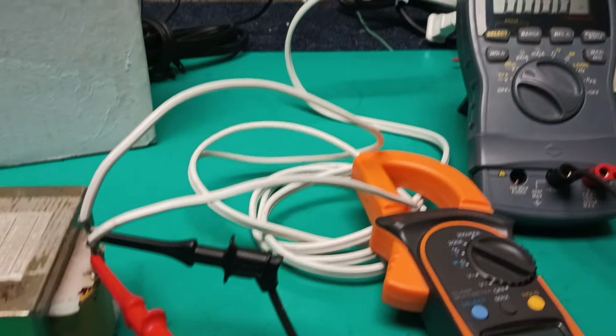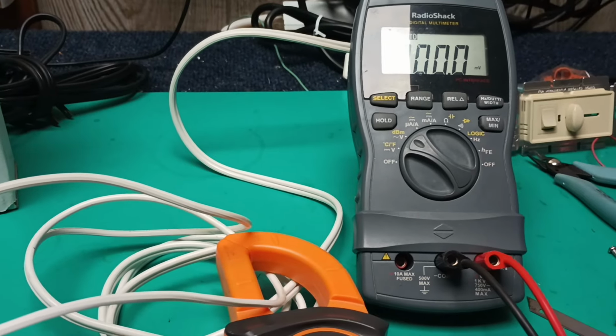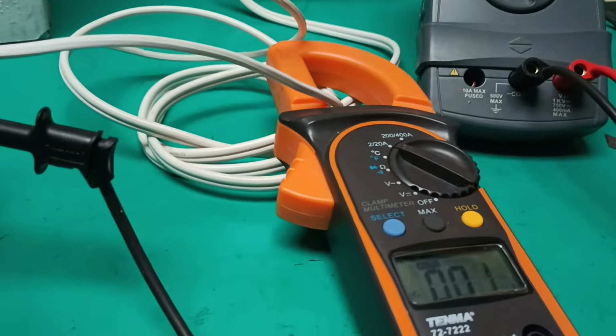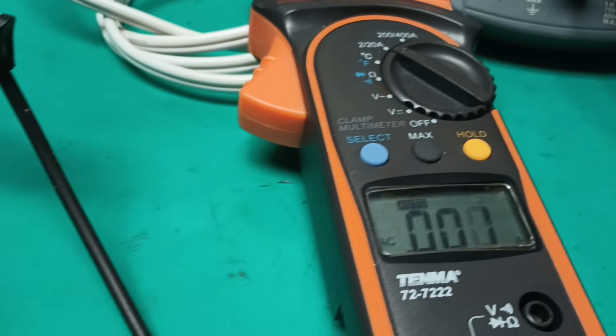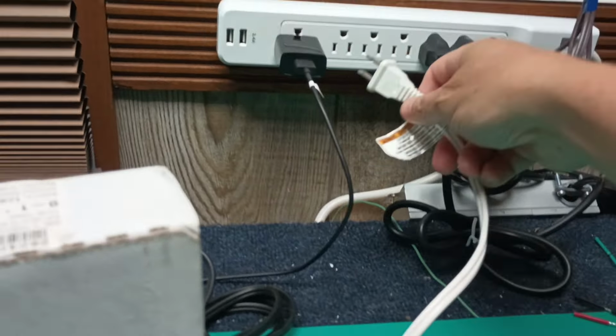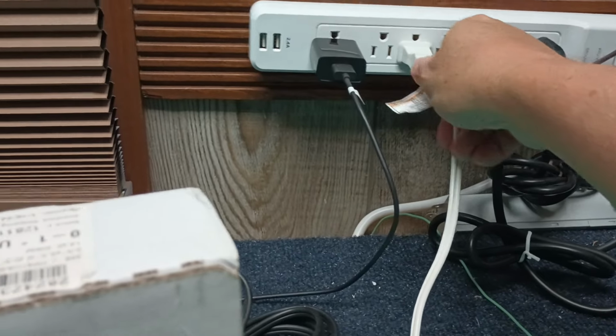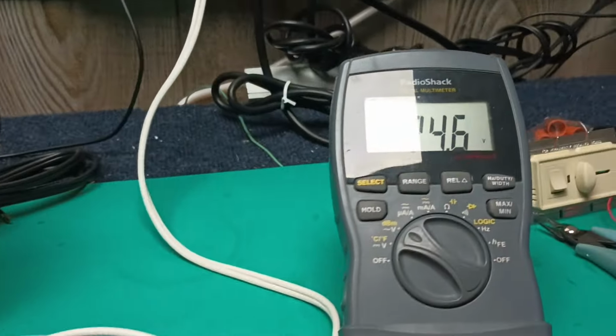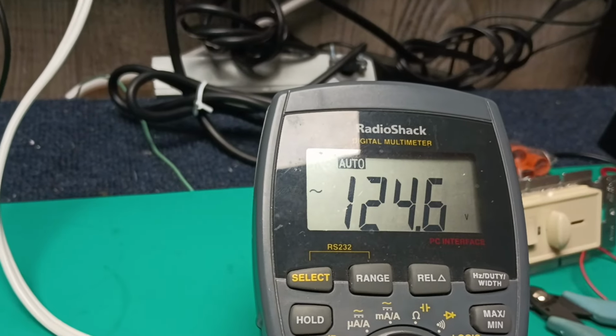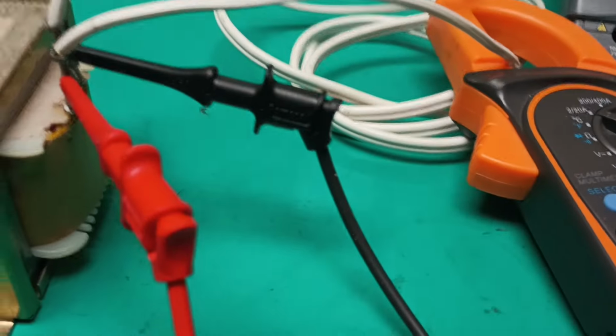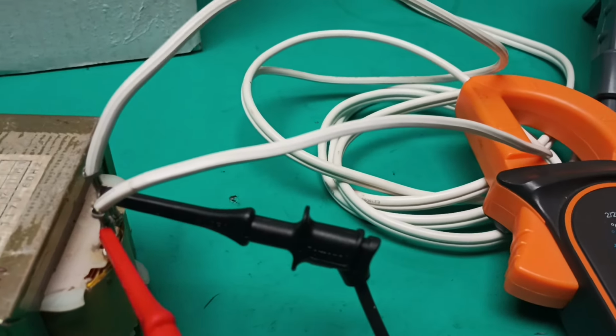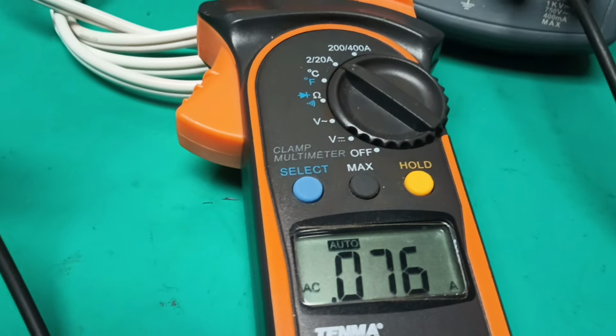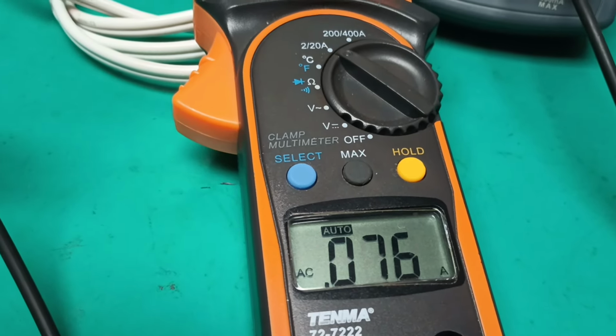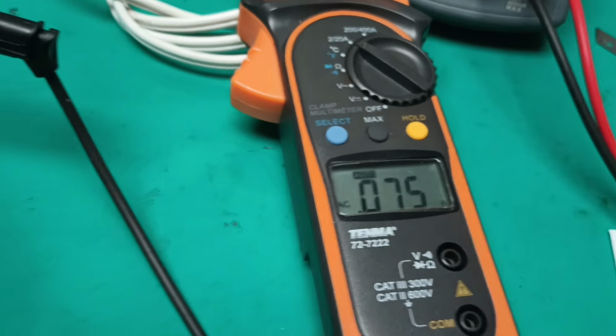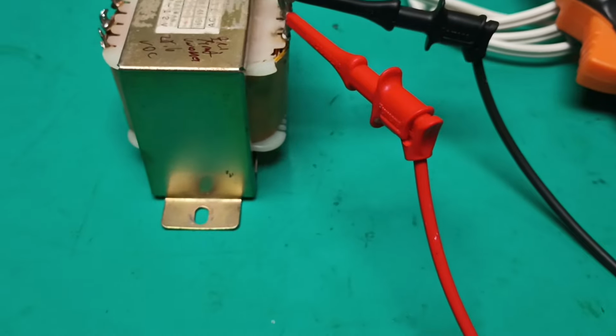So first step, get a decent digital multimeter. That isn't one, but it's cheap. For convenience, I've got an amp clamp like used in HVAC, transformer, cheater cord. Of course, no fuse. We know what we're doing, don't we? So we plug that puppy in, and we read across the primary 124.6 volts AC from the AC line. And with a current clamp and one wire to the transformer, we read this transformer is wasting 76 milliamp at 124.5 volts AC. That's power doing nothing except heating the copper windings in the core.